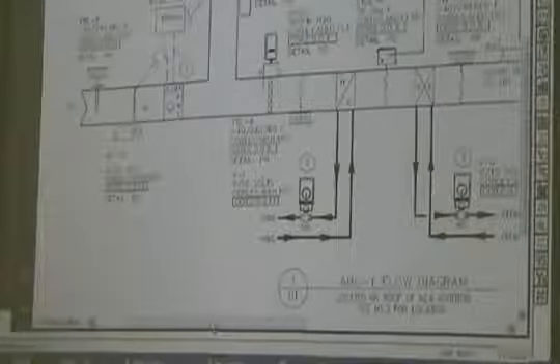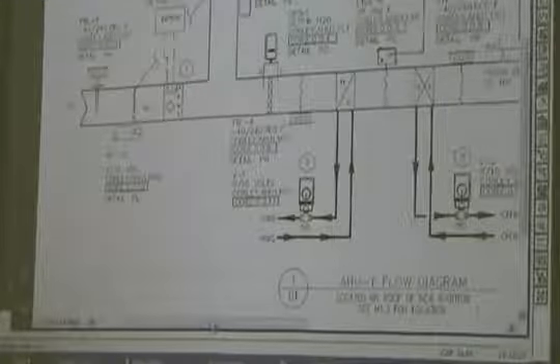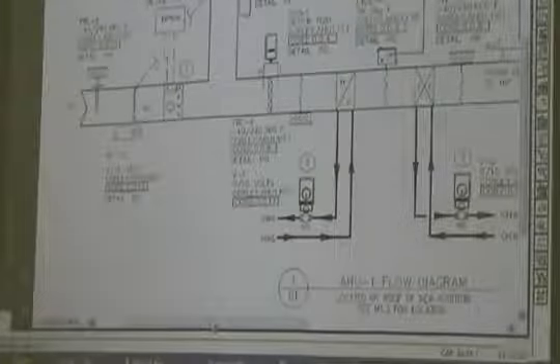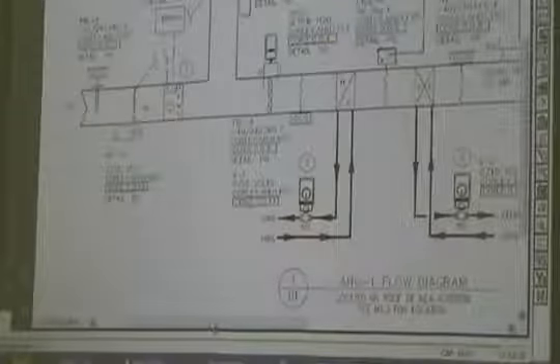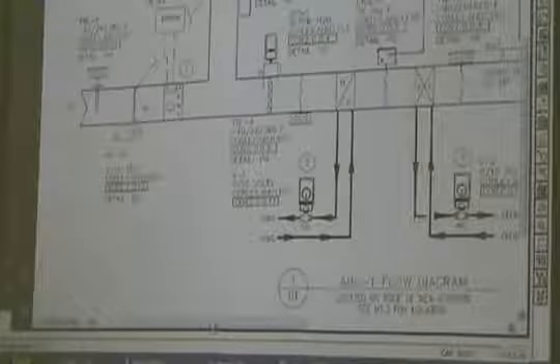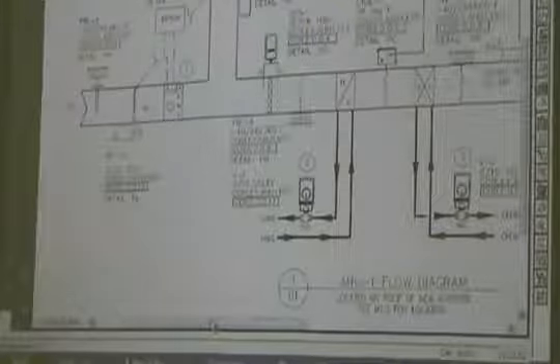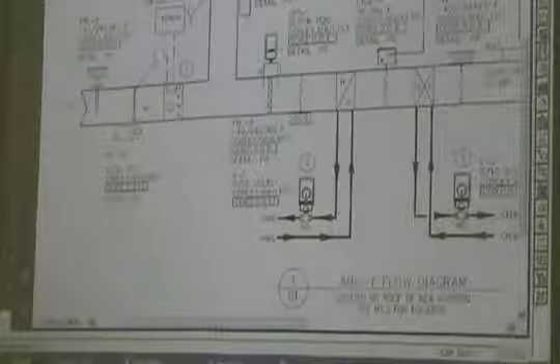Now, what are we going to do with that? When it's cool outside, most all our air handlers are for cooling, so we're trying to maintain 55-degree air leaving the air handler. If it's below, what temperature outside would we start using outdoor air? What would we want to start using outdoor air? What's our return air temp going to be? 72-ish, 75, depending on what we're keeping our space at. So is it cheaper to use return air or outdoor air to supply the air handler? Outside, if it's below.